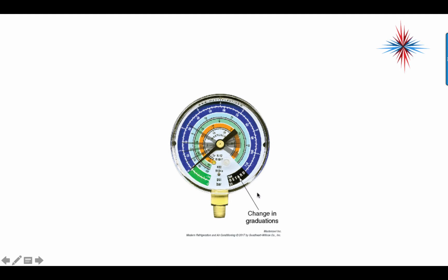Okay, and this picture here shows it. We have the green, which is a vacuum, so that's going to be a negative pressure. Then all of a sudden, when you get up over like 125, we go into what's called the retard mode. Okay, and that will give the measurements up to 340. In other words, it's a little bit of a different spring and a little bit of a different accuracy.